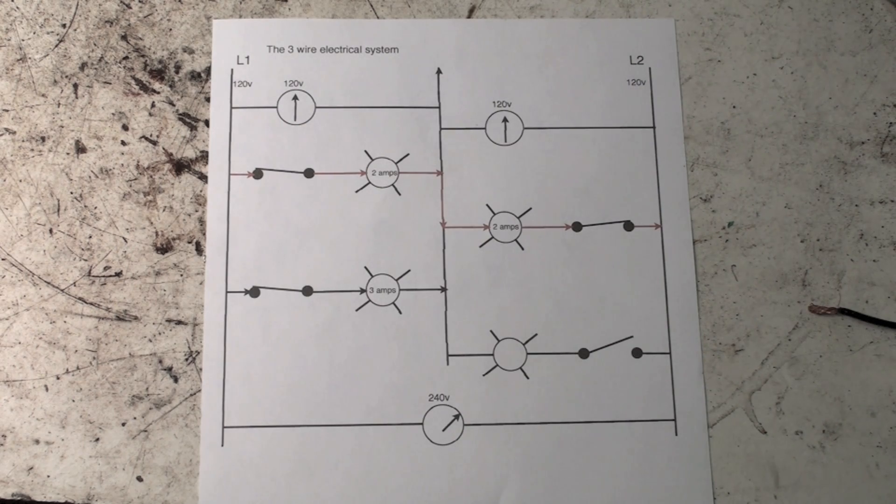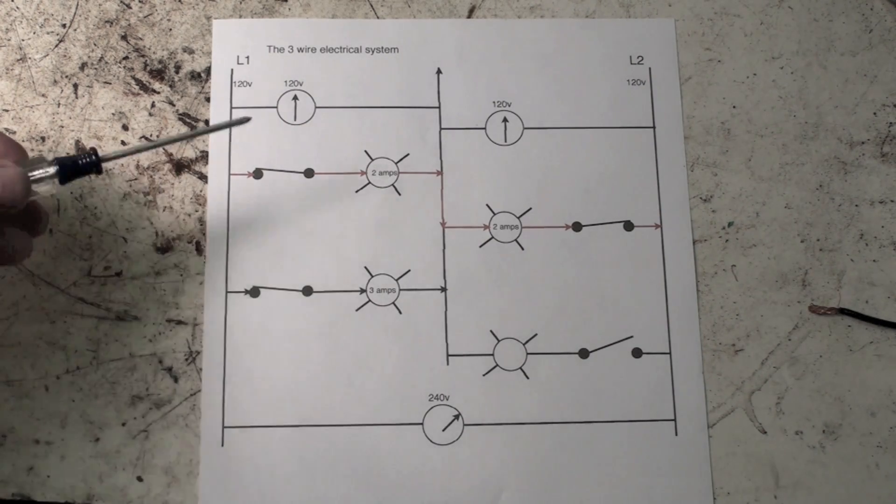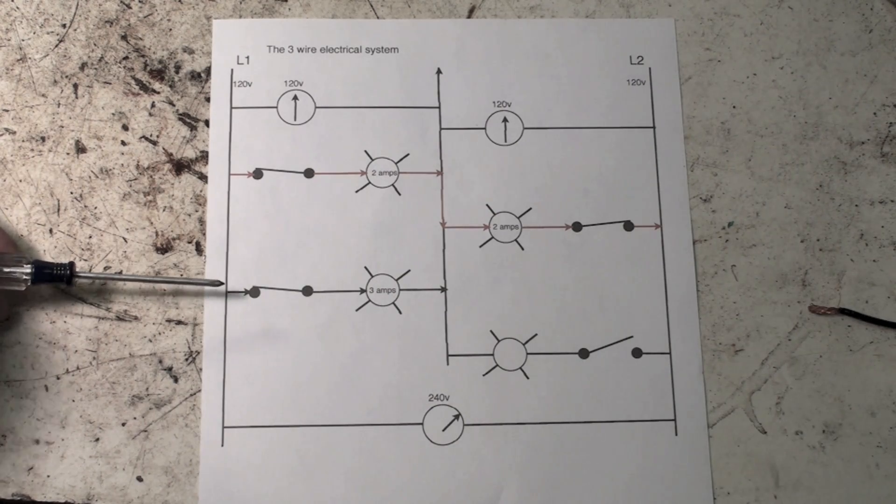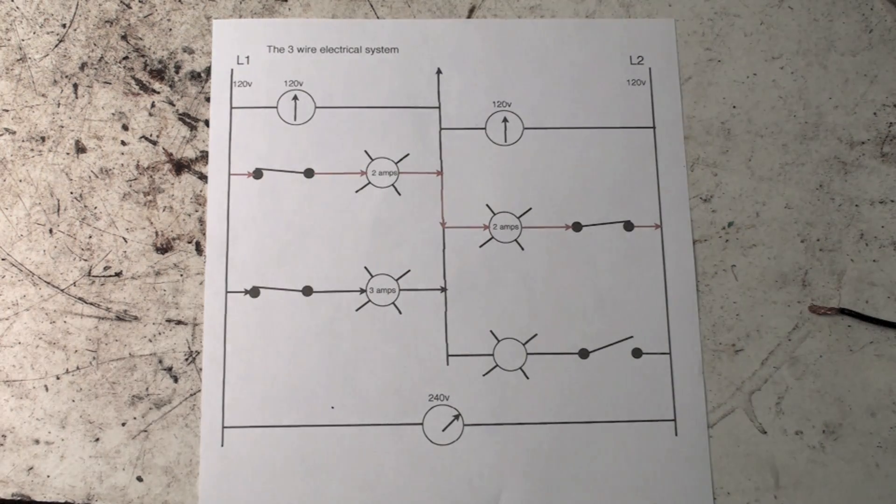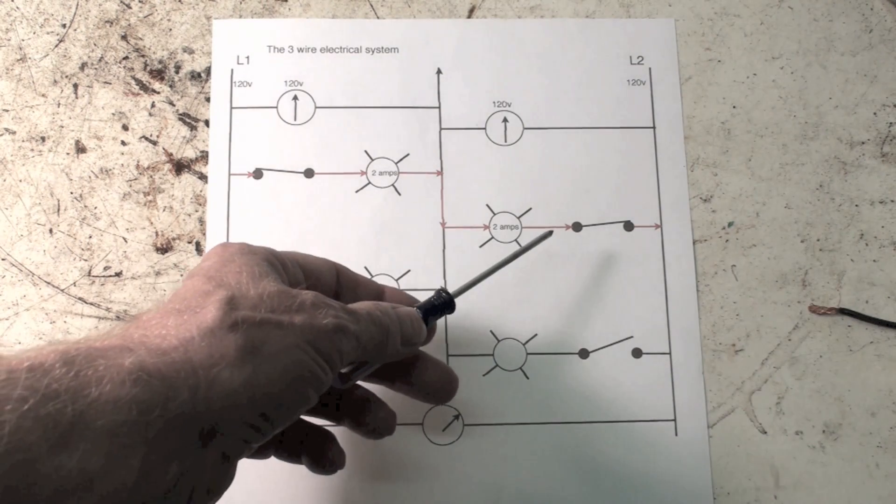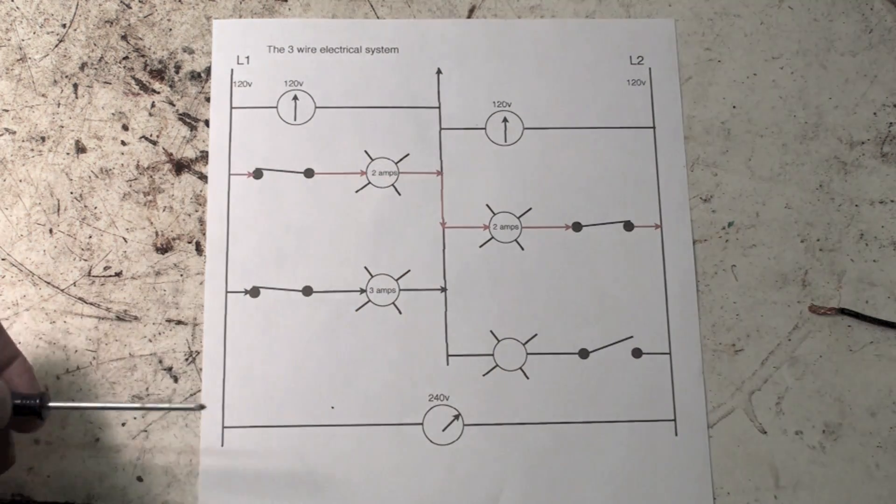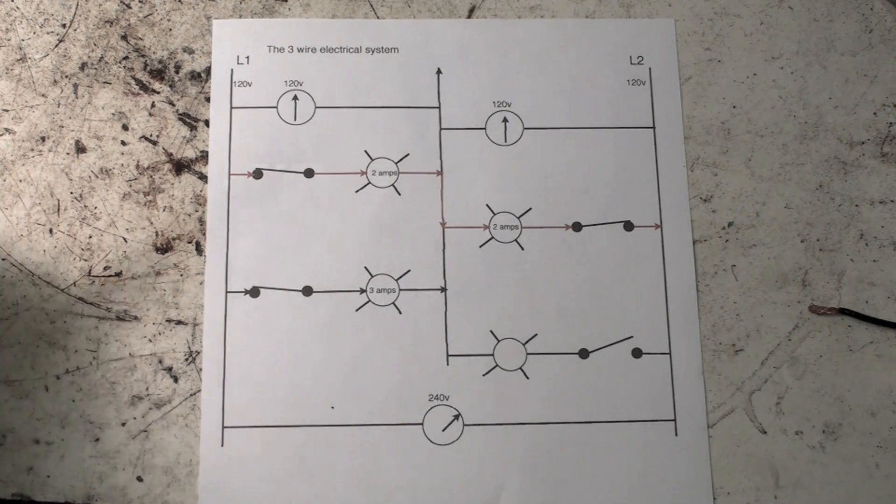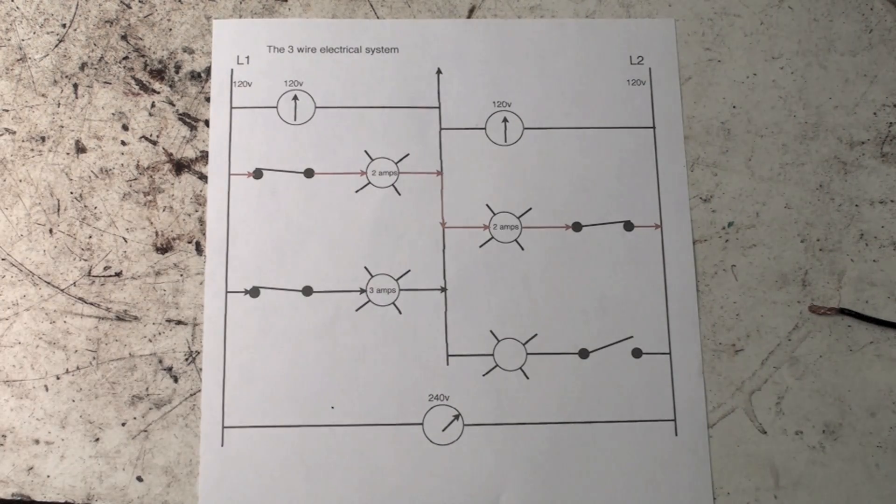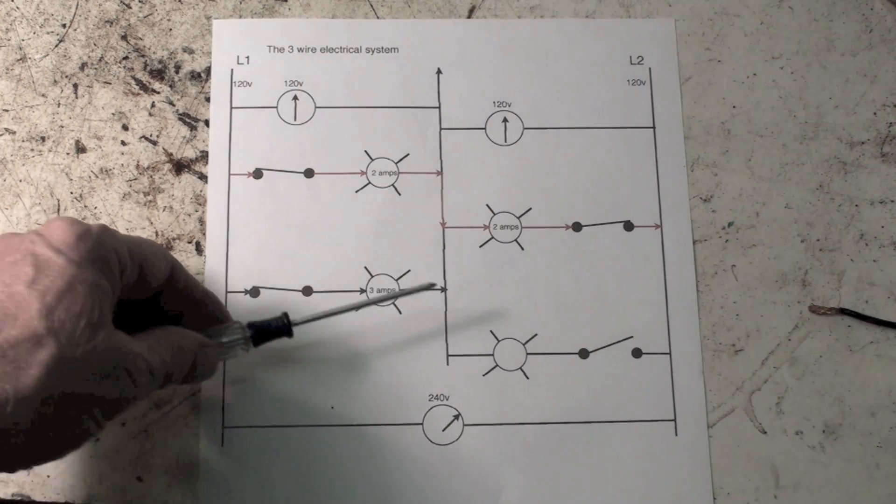If I go down here, I've got a 3-amp load, and I've got another load over here but it's open. So where does that three amps go? It can't go through here because this is already going through there, so it goes to the neutral line. Now if there are other loads in this panel that can accommodate that 3-amp load, then it does.